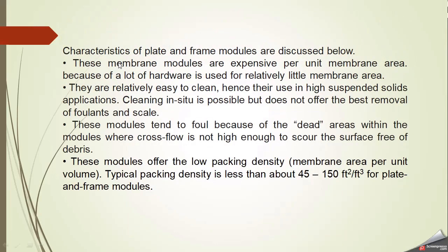Some of the main characteristics of this plate and frame module are discussed below. These modules are expensive per unit membrane area because, due to their construction, a lot of hardware is used for relatively little membrane area. They are relatively easy to clean. This is a benefit, hence their use in high suspended solid applications. Cleaning in situ is possible but does not offer the best removal of foulants and scales.